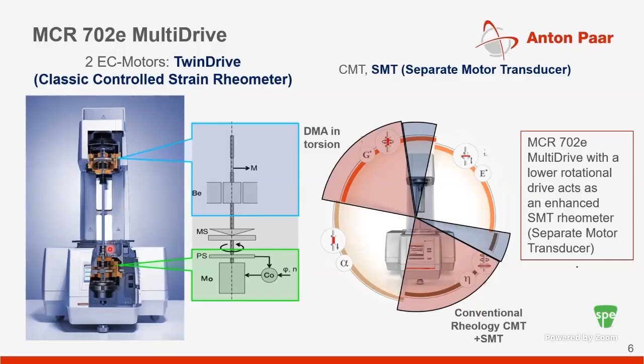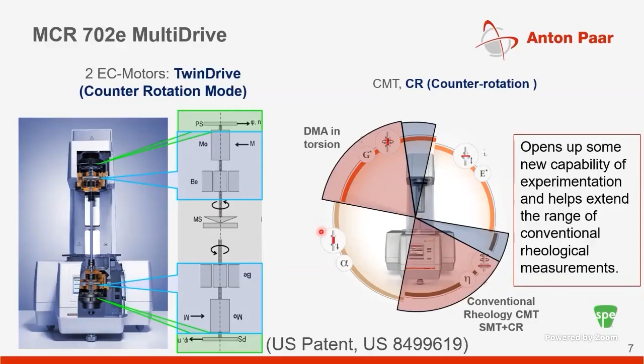Since you have two motors, you can also do unique experiments where they rotate in opposite directions, enabling counter rotation type experiments very unique to this multi-drive setup. Both drives oscillate in opposite directions, with the speed or angle equally distributed between the two drive units, while torque and normal force data come from the top motor to calculate rheological properties. This really opens up new capabilities and extends the range of conventional rheological measurements, which I'll show through several application examples throughout the talk.